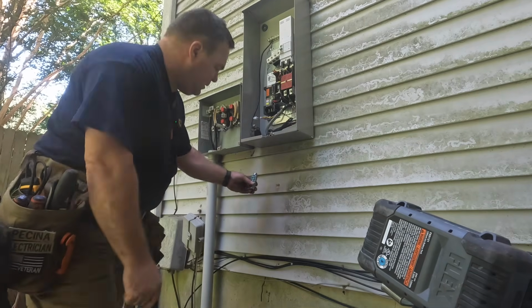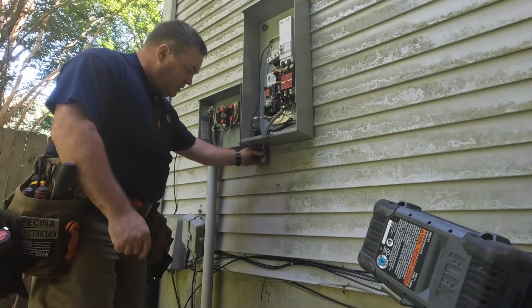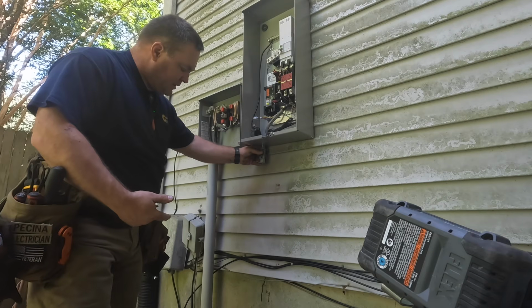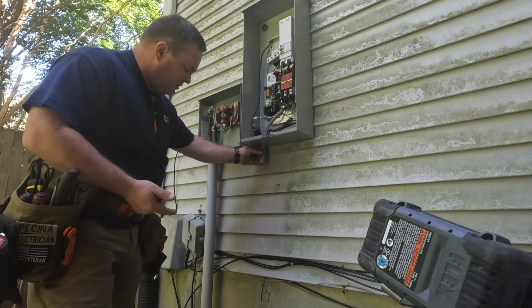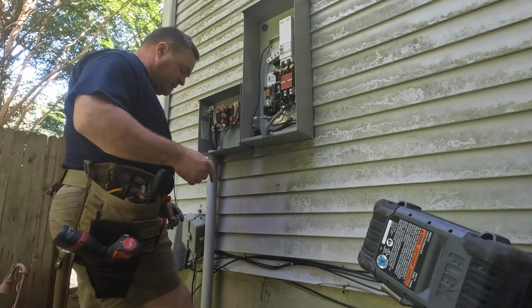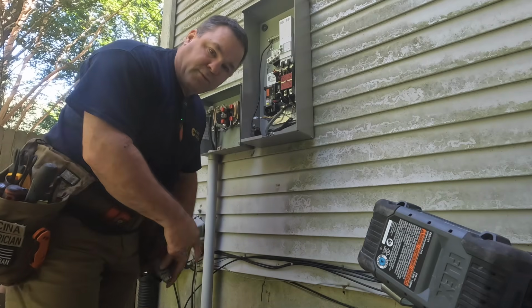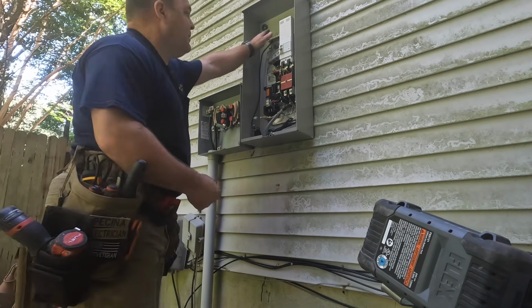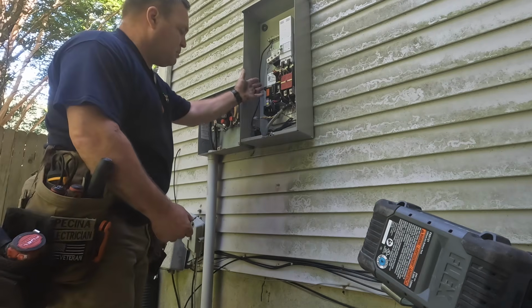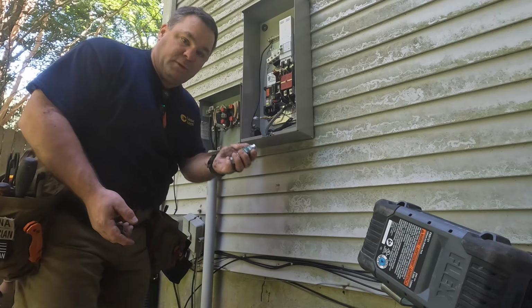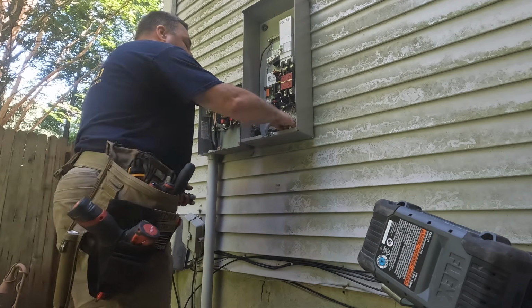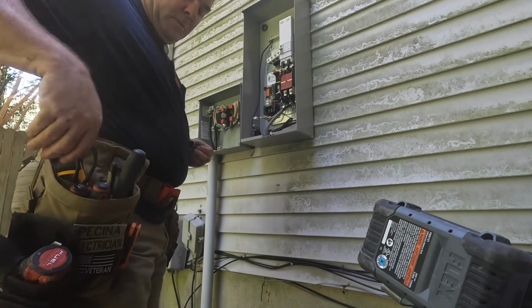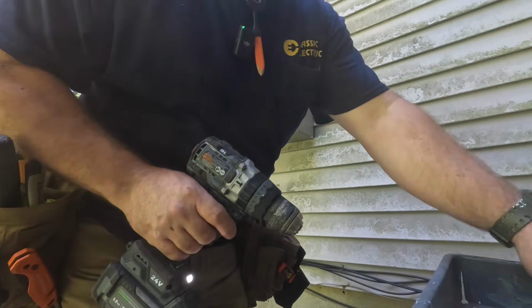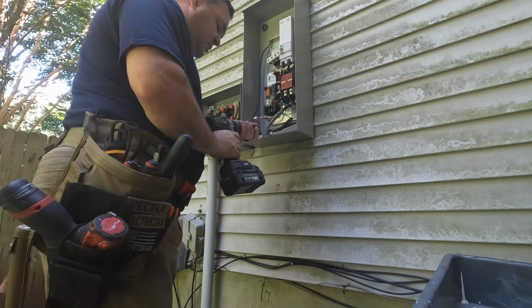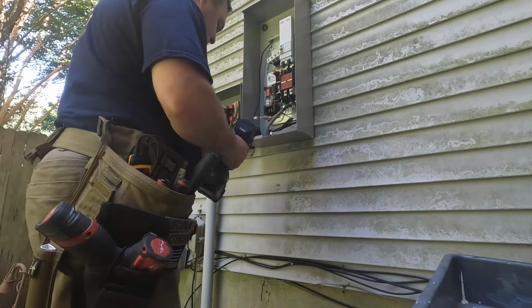This will sit right underneath here. Definitely not required to do this right now, but it just seems fitting, just to clean this up, because this conductor, the grounding electrode conductor from the ground rod up to my main here, was a little short. So instead of doing a splice in here, we'll just redo it. And since we're redoing it, now I got to add this. This is a better job, not necessary, but it's going a little bit more than what's required, which is fine, obviously.